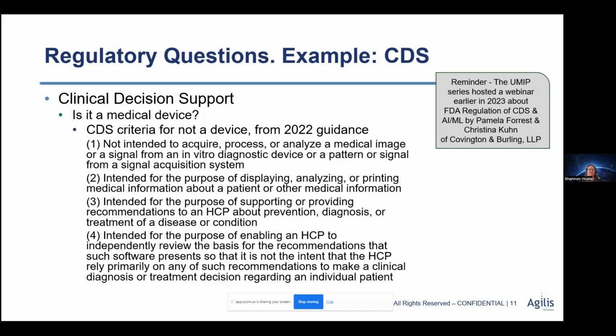When we look at the clinical decision support guidance, what it is a guidance for is to help you determine if your software tool, that is a CDS tool, is a medical device or not. And so what it was providing were 4 criteria for what makes your product not a medical device. So it walks through: it's not intended to acquire, process, or analyze imaging or signals, right? It's solely intended to display or print medical information. It's intended to support recommendations, right, but not give specific recommendations. And finally, it's intended to enable HCPs to independently review the basis for those recommendations.